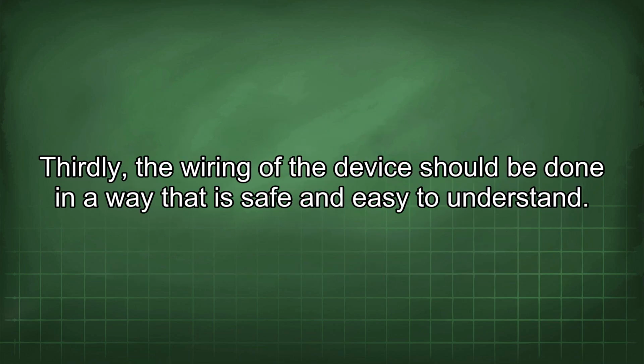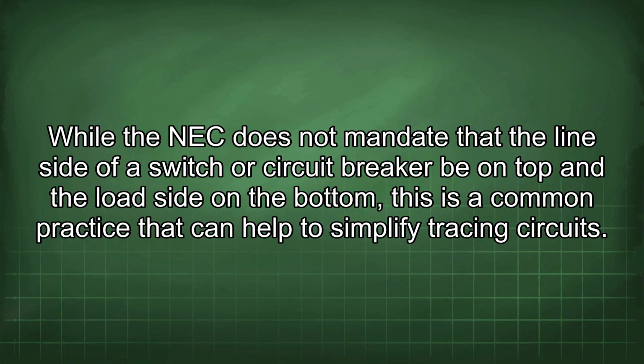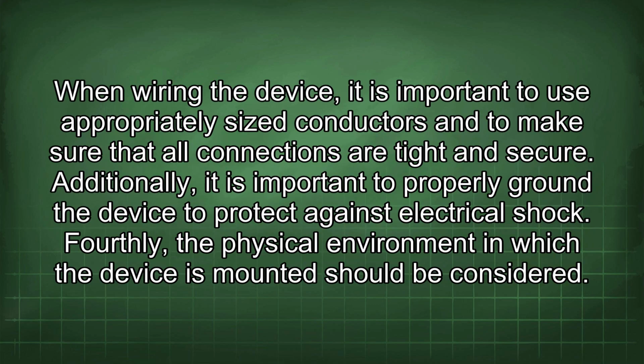Thirdly, the wiring of the device should be done in a way that is safe and easy to understand. While the NEC does not mandate that the line side of a switch or circuit breaker be on top and the load side on the bottom, this is a common practice that can help to simplify tracing circuits. When wiring the device, it is important to use appropriately sized conductors and to make sure that all connections are tight and secure. Additionally, it is important to properly ground the device to protect against electrical shock.